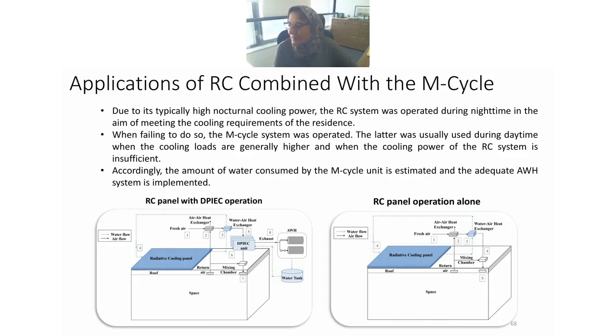At point 4, the cooled air exiting the water heat exchanger at 5 is supplied to the cross-flow dew point indirect evaporative cooler system to be cooled to the correct flow rate and the correct temperature that you need for the supply. That product air could be mixed with the return air based on the fresh air requirement of the system. As I said, the water harvesting system has a batch system formed of several sorbent beds. You have a daily cyclic sorption and desorption of the airstream that comes from the dew point indirect evaporative cooler, and the collected water vapor is condensed and stored in a tank for future use.